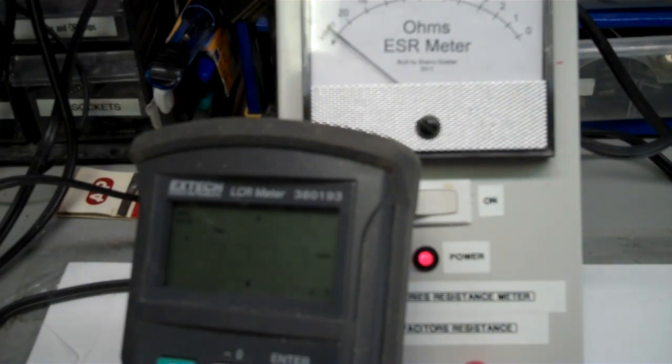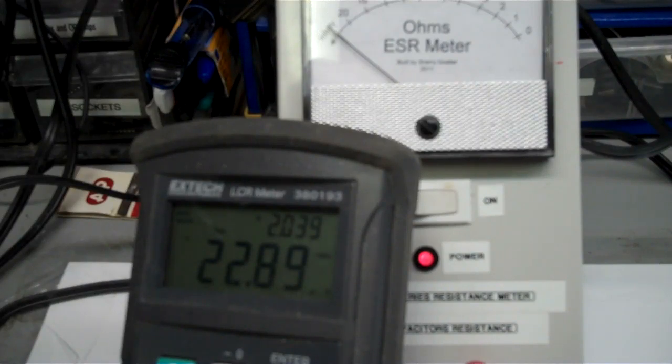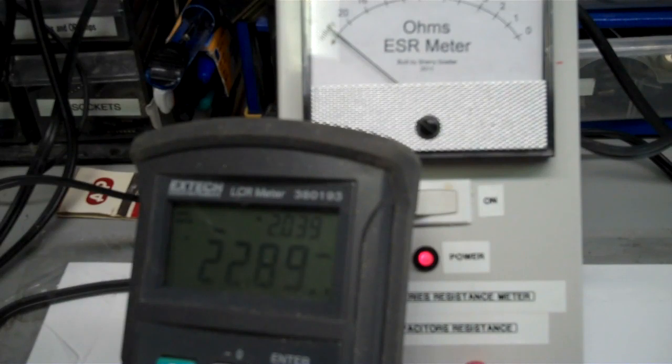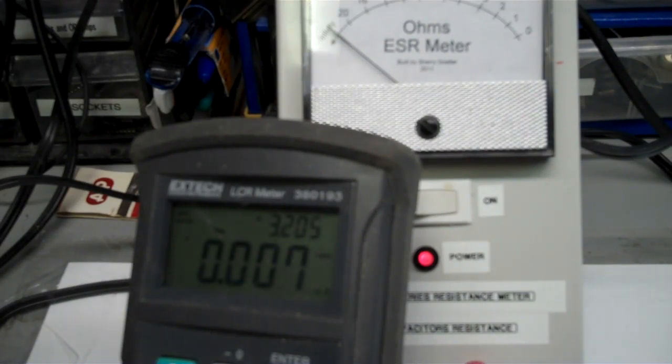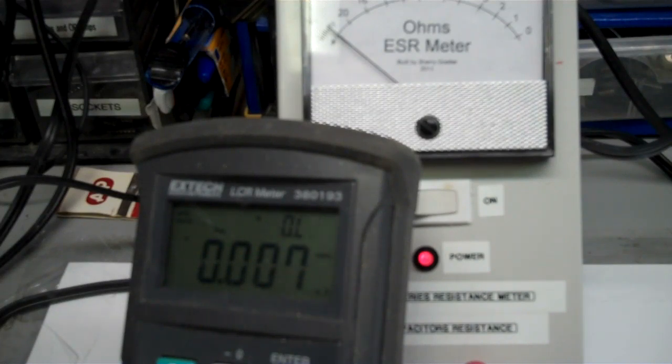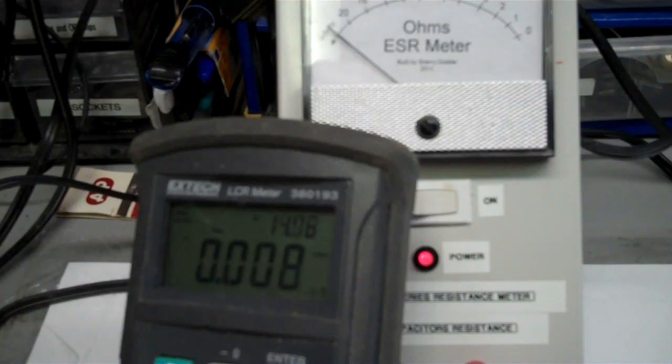And like I said, it's 100 microfarad. Okay, well, this capacitor is reading bad altogether. So it's actually reading 22 microfarad when it should be 100. But sometimes what you'll find is capacitors are, they check fine on a capacitance meter. You'll see it close to the value printed on it. However, when you check the resistance of it, the AC resistance, you'll see that it's bad.